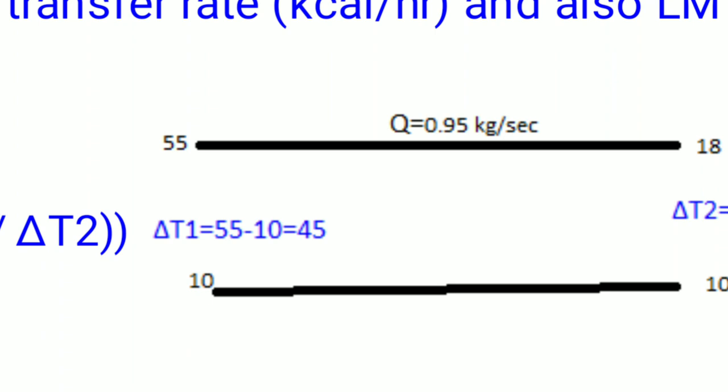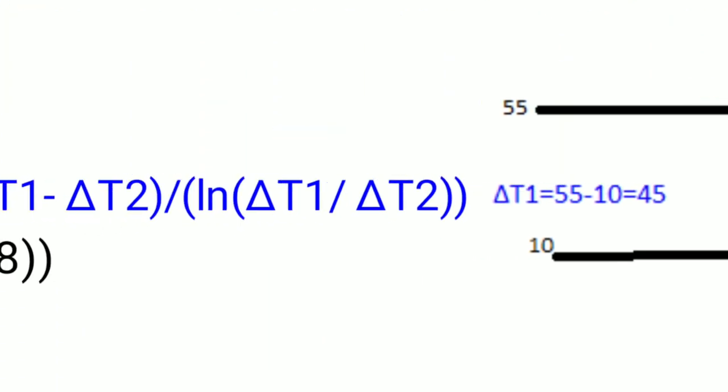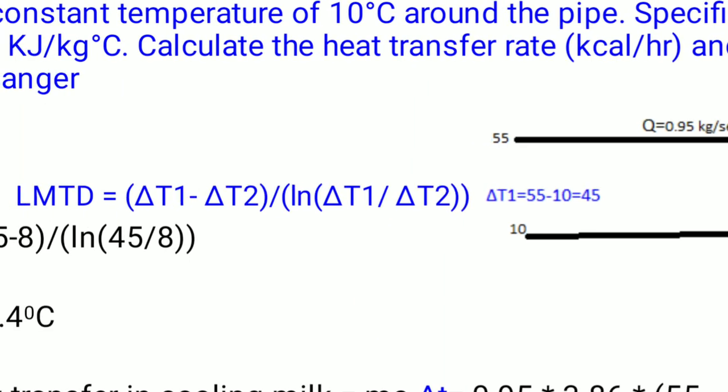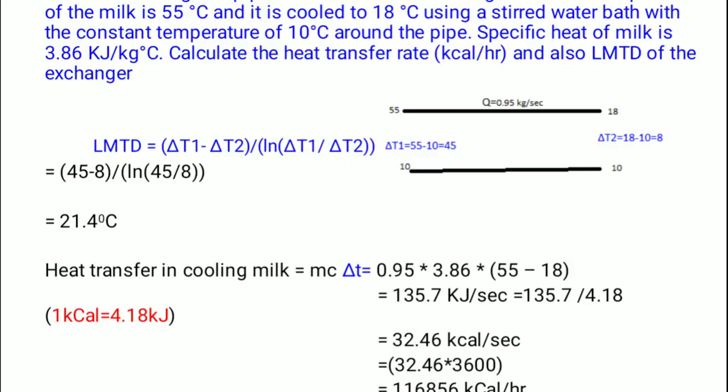Milk enters at 55°C and leaves at 18°C. The water bath is at a constant 10°C at both entrance and exit. So delta T1 = 55 − 10 = 45°C, and delta T2 = 18 − 10 = 8°C. Substituting into the LMTD formula: LMTD = (45 − 8) / ln(45/8) = 21.4°C.